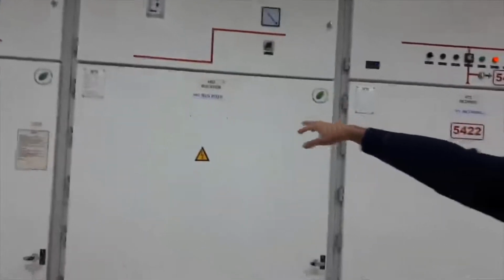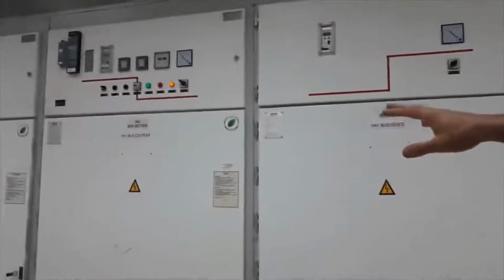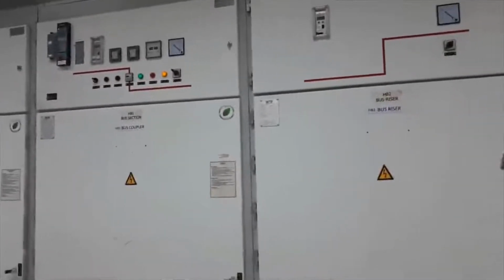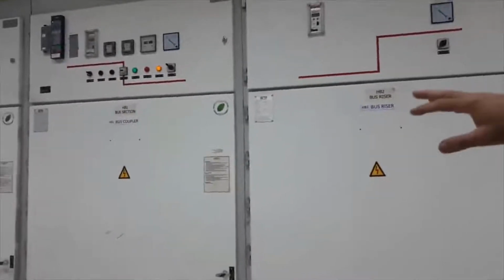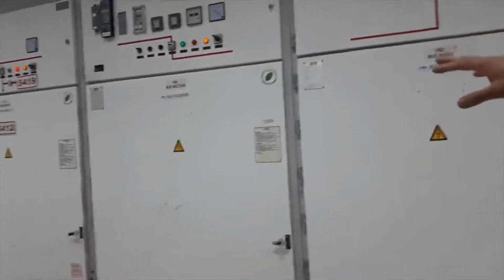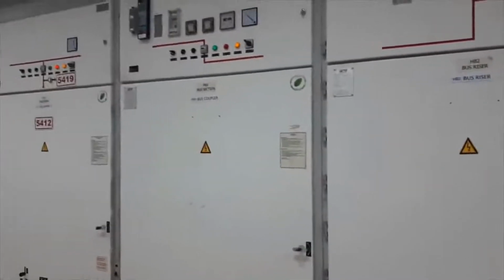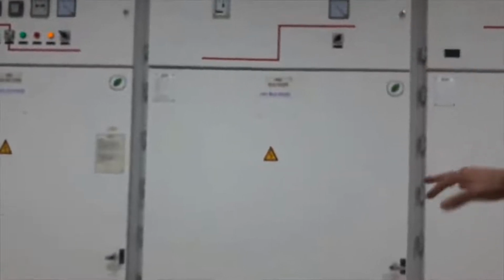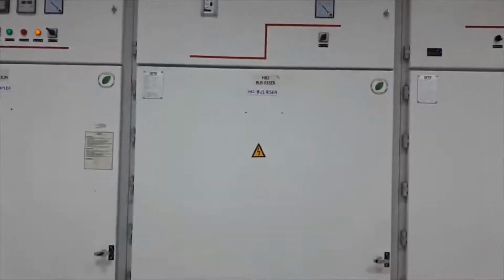We have one bus riser cell and one bus coupler cell. Inside the bus coupler cell, there is a breaker that connects bus number 1 to bus number 2. Bus riser in this cell raises the bus bar at the bottom of the breaker and connects it to the next bus.